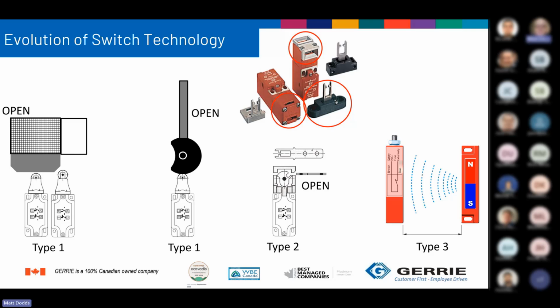And then type 3 introduces the concept of non-contact sensing. In this example, again, magnets are being used to keep a set of contacts closed. However, other styles of sensing exist: optical, inductive, capacitance, ultrasonic. Type 3 devices, while not my first choice, can help solve certain challenges and can have advantages in select applications with higher current direct switching capabilities and sealed explosion-proof models. However, a means still needs to be provided to prevent unintended actuation of the switch.